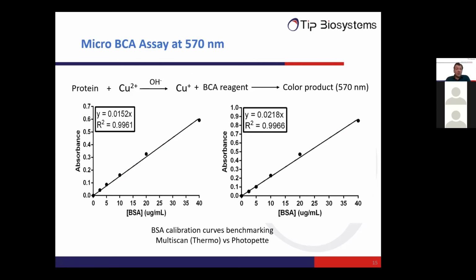This is another very common assay that we have in the life science lab to measure protein concentration. It's a BCA assay, which is based on a copper 2+ ion. And this then forms a colored product with protein, which can be read out at 570 nanometer. That is a wavelength we have, for example, in the Photopette cell. And also here you see a calibration curve using bovine serum albumin, for a standard big benchtop spectrophotometer, a Multiskan from Thermo, versus the rather small Photopette device. So the Photopette here has a slightly higher slope, which is basically an advantage over the other instrument.